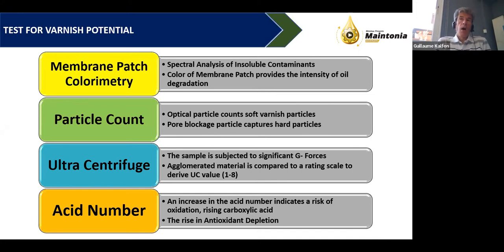The other upside of MPC is that it is a standard method, a global standard under ASTM code D7843. So all labs that are accredited for D7843, it means that there is reproducibility between the laboratories.